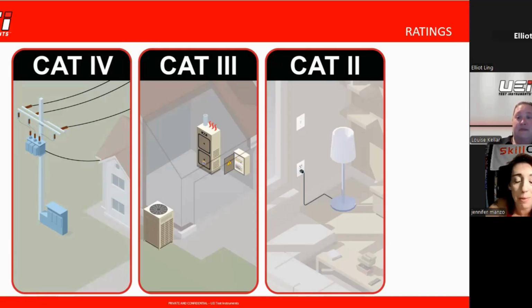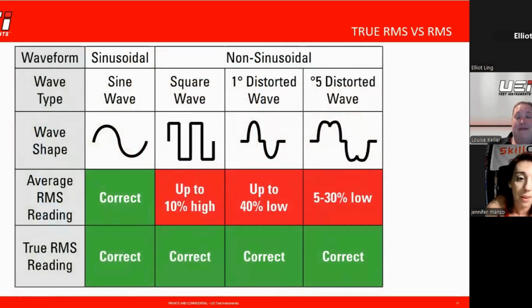I've seen so many meters get blown up just because voltages were crossed in the disconnect, on HVAC equipment. I've seen Cat 3 meters get cooked that way because it really needed a Cat 4 and somebody wired it wrong. It's a very distinct safety feature that will save you a lot of trouble. I am a big fan of that.